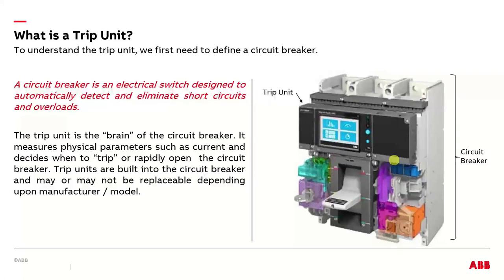So I'm calling the trip unit the brain of the circuit breaker. It basically measures physical parameters, and mostly that's current. And then it decides whether or not to open or trip the breaker. And they're built into the circuit breaker in these cases, and it may or may not be changeable or replaceable depending on the manufacturer or model. There's a wide variety of different types, styles and designs of circuit breakers from various manufacturers over the years, so it's a pretty broad topic.